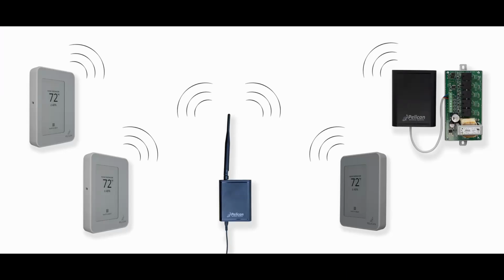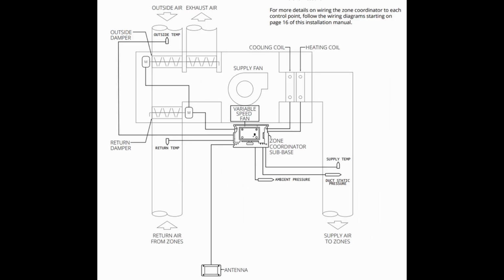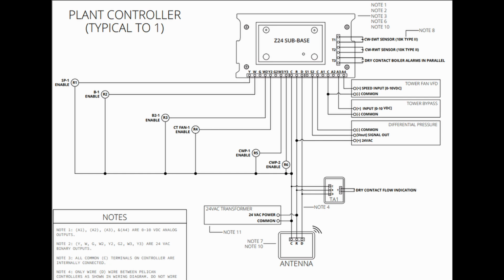Once your new Pelican system is installed, you will have many thermostats which will need the plant to be operating before they can run heating or cooling. Once properly configured, the thermostats will send a signal through the mesh network to enable the plant equipment. Pelican wireless control systems are highly adaptable and in many cases can be tailored to your needs. Many wiring diagrams can be found in the documentation provided with your Pelican controller, or on the Pelican Wireless website. Also, custom diagrams for your application can be provided. Contact Pelican Wireless technical support to see what components will work best with your specific application and for help with configuration.